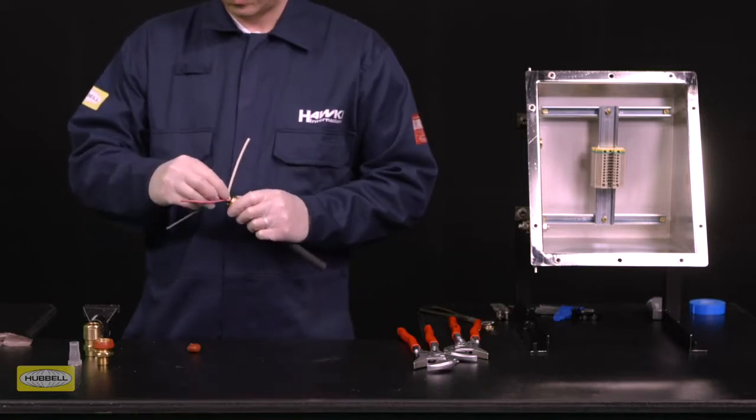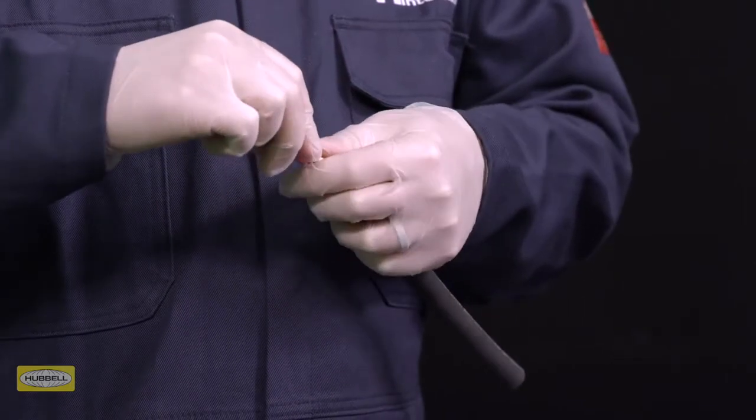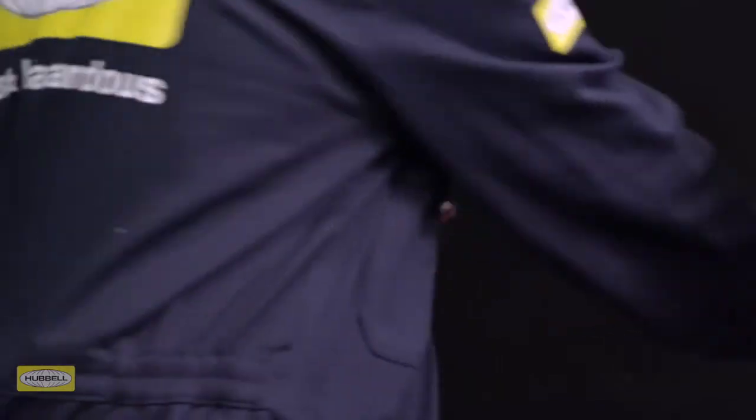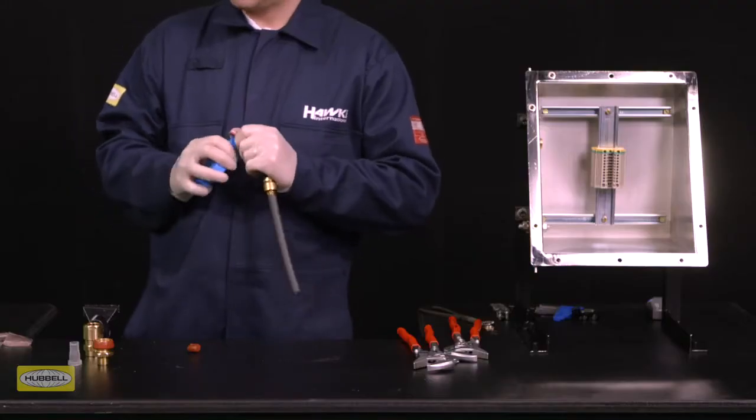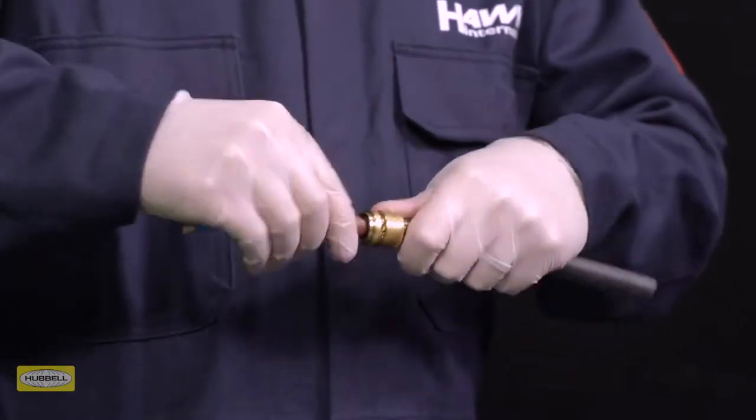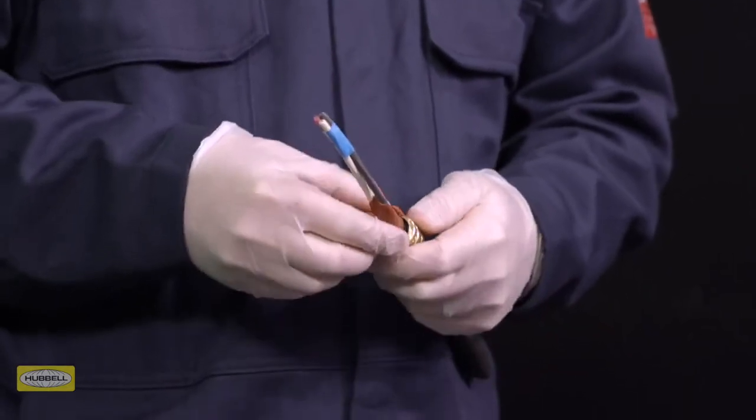Spread the cable cores and pack the compound between the cores. A cylindrical shape is the best way to ensure that the compound is effectively packed between the cores. Once all the gaps and voids have been filled, bring the conductors back together. Tape the conductors together to prevent disturbance of the compound seal whilst packing.